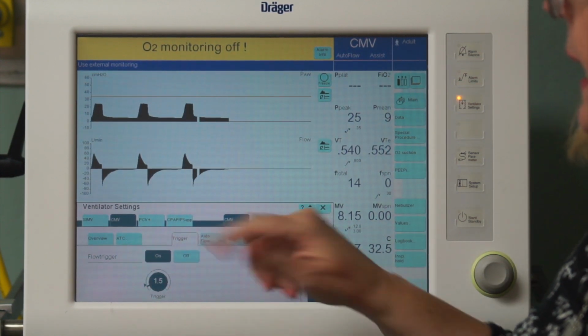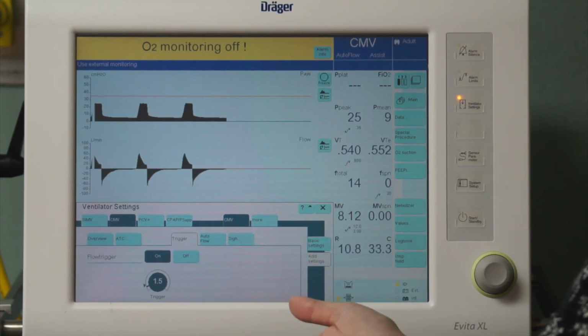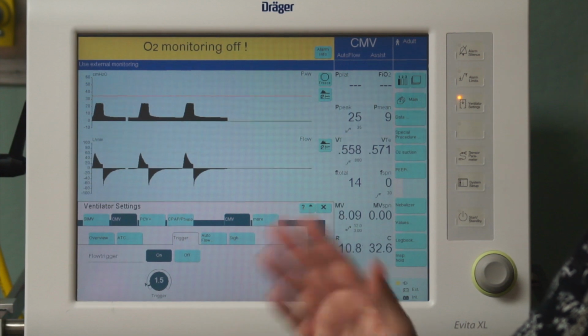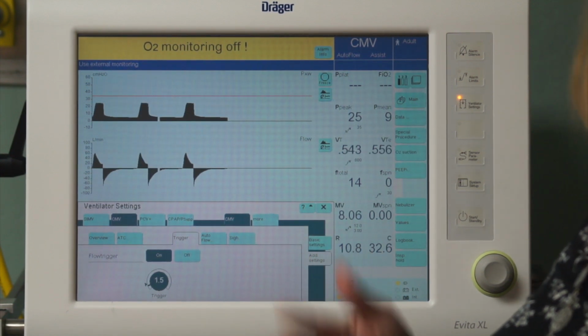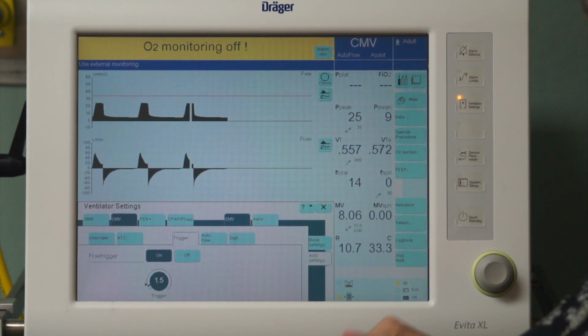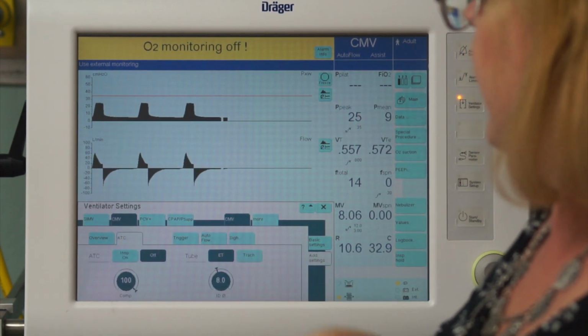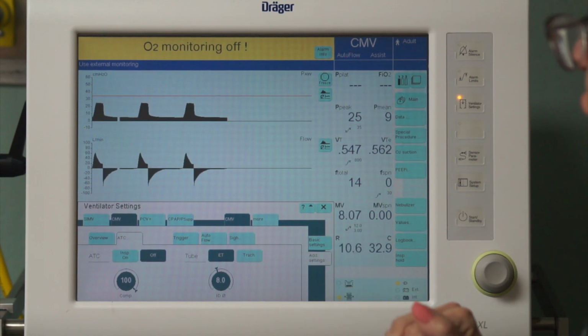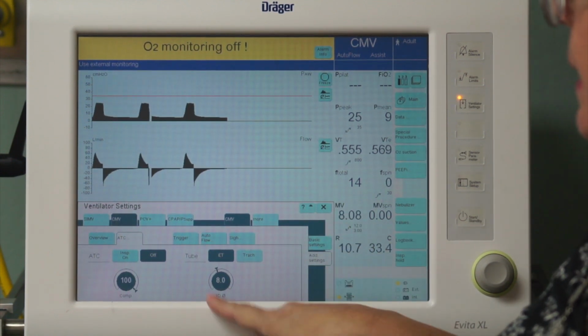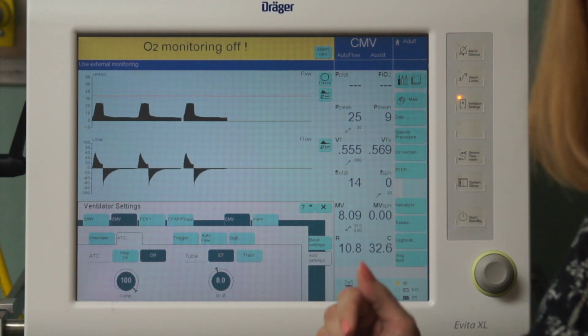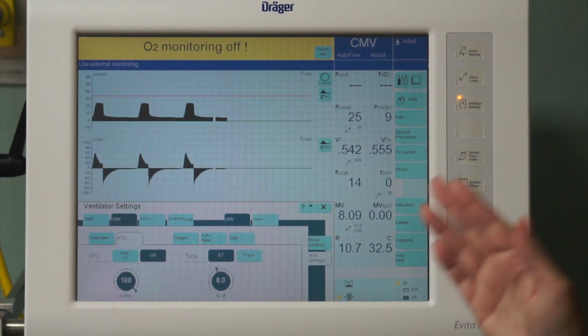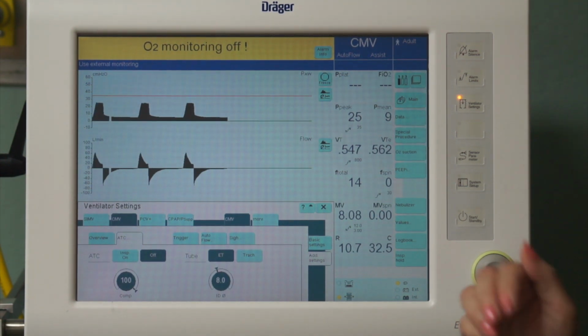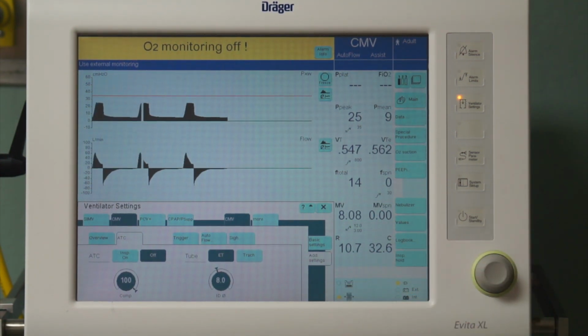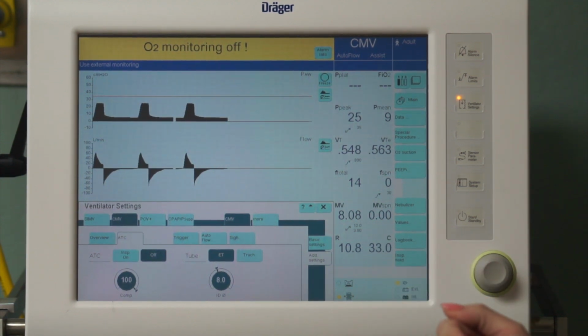And so this is flow triggering, and I could turn that off. So if it was a patient that had a huge leak, like a trach patient, something that didn't have a cuff, then I could turn that off, and then I would be in pressure triggering. Another feature here that you may want to use or not use, depending on your patient, is something we call ATC. Now, what is ATC? ATC is automatic tube compensation. This is something that is not always used, but it can be very helpful, especially with smaller ET tubes, because as you know, the smaller the ET tube, the more resistance you have.